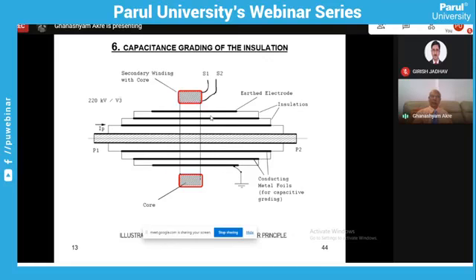The long life of the transformer is also important, because these are hermetically sealed transformers. Their life has to be 20 to 25 years. There is no chance of changing the oil, or filtering and drying it if it catches moisture. So once you install it, it should work for 20 to 25 years without any problem. Otherwise, they fail disastrously, because they generally explode like a bomb, and at the same time they damage the surrounding equipment also.